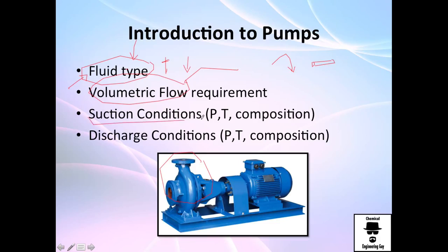You need to know definitely the suction conditions: pressure, temperature, and composition. Pressure matters because we might have a very low pressure, and therefore you will not be able to operate it, because when the fluid gets into the eye of the pump, it's going to evaporate and will cavitate your pump.